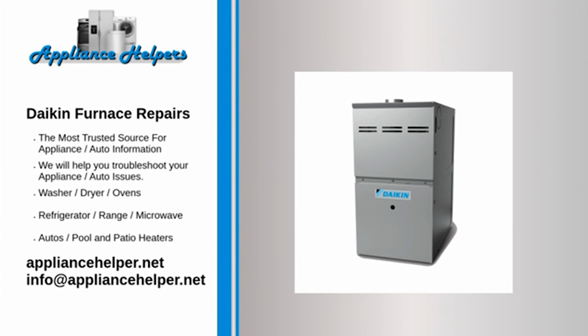The air coming from the furnace smells bad. Foul odors from the furnace are usually caused by a very dirty filter that should be washed, if washable, or replaced. Another cause is a dead rodent or bird somewhere in the system, usually a job for a professional furnace technician.